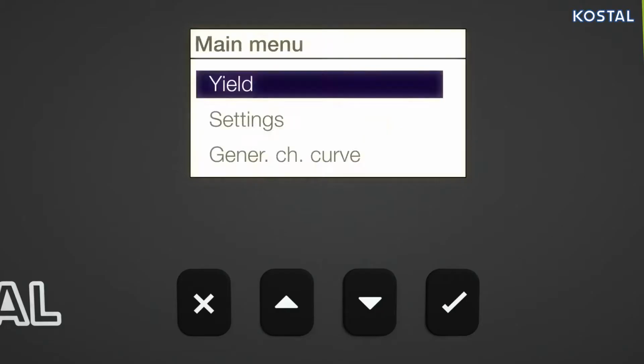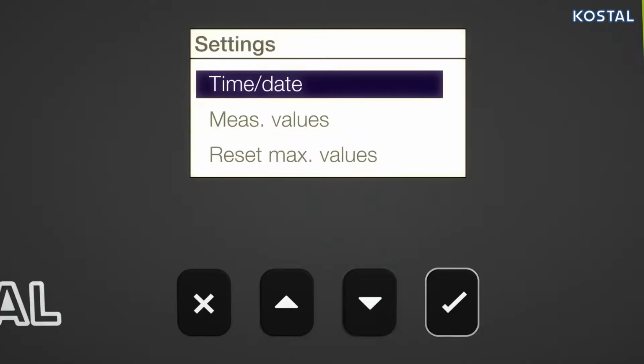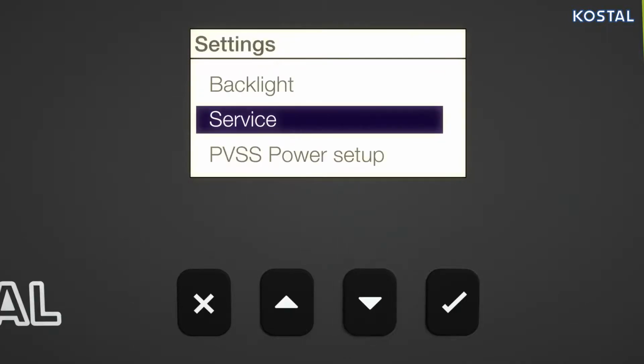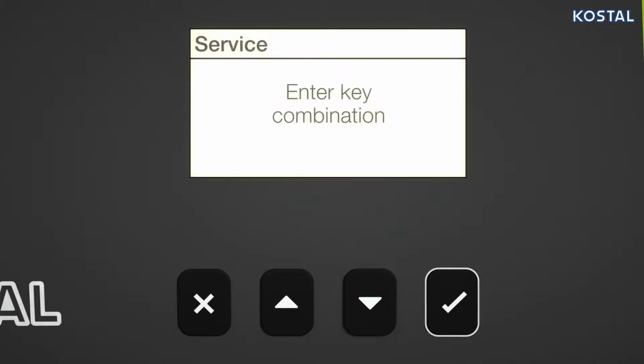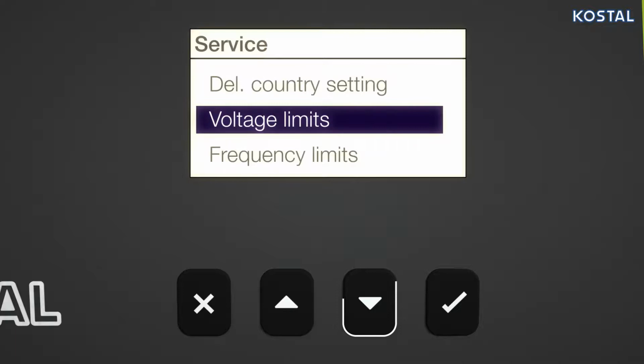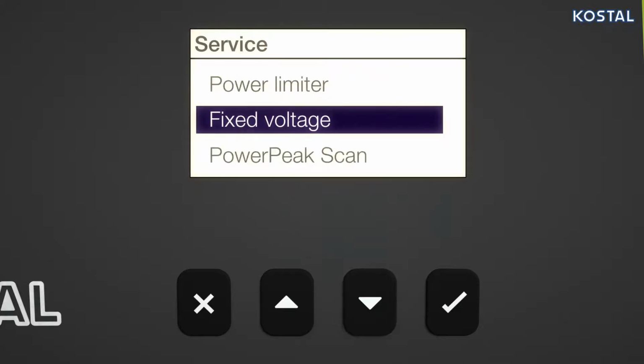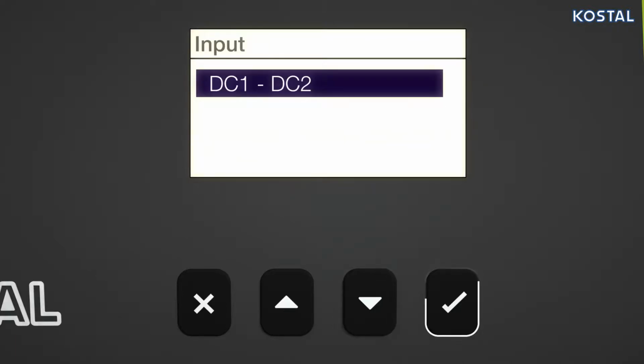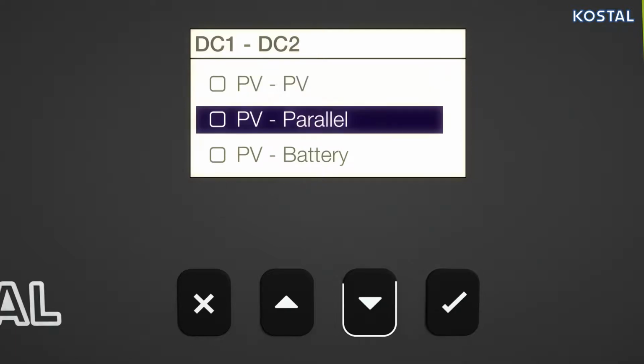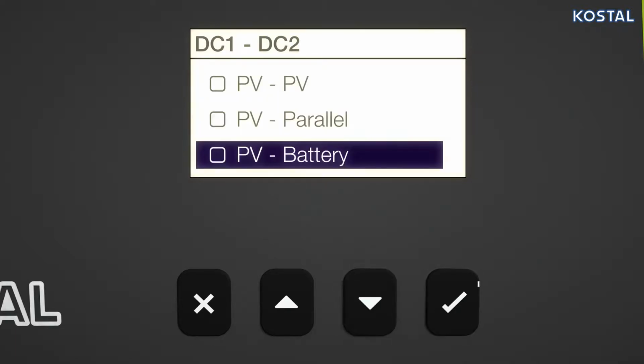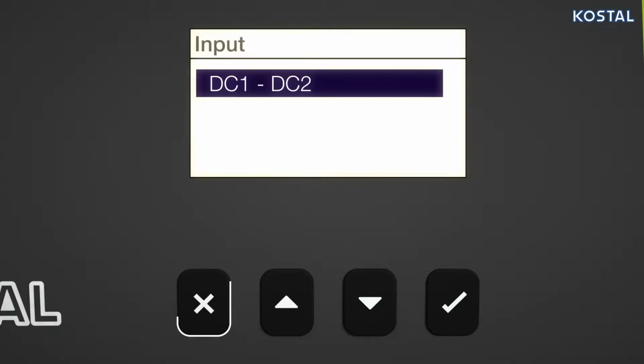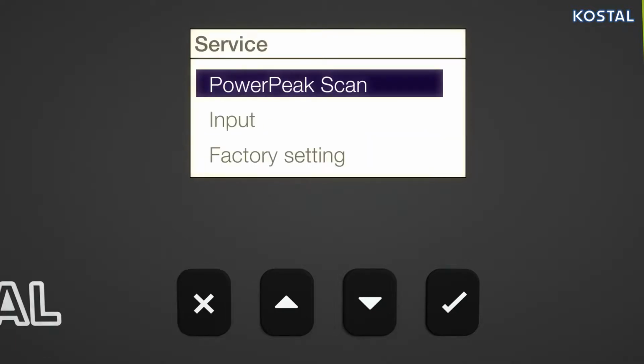Enter the inverter's main menu and use the arrow keys to go to Settings and then Service. Press the 2 arrow keys here at the same time for a few seconds. This opens the service menu. You can now switch the DC input to battery operation using the menu item Inputs. The DC input is thereby switched to battery operation. Use the Escape key to exit the menu.